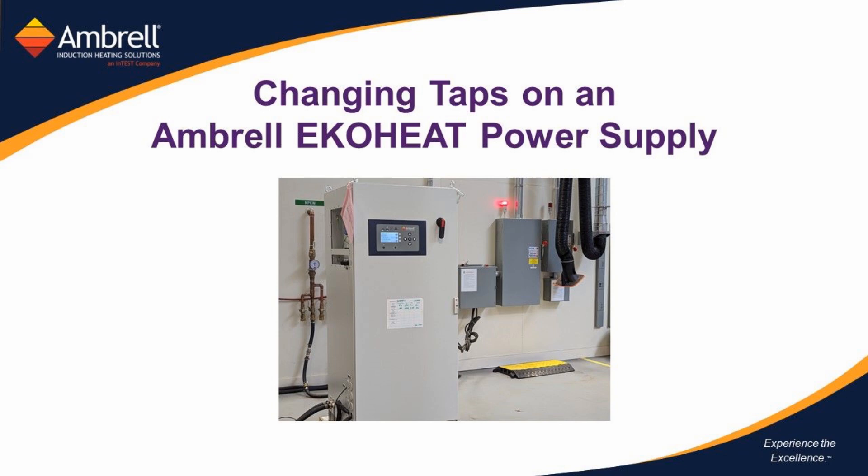This video will cover changing taps on an Ambrell EKOHEAT power supply. Changing taps on an induction power supply is similar to changing gears on an automobile, or changing the feed rate or spindle speed on a mill. No one setting is ideal for all applications. Ambrell has made this process easy as it can be accomplished with only a few simple steps and tools.